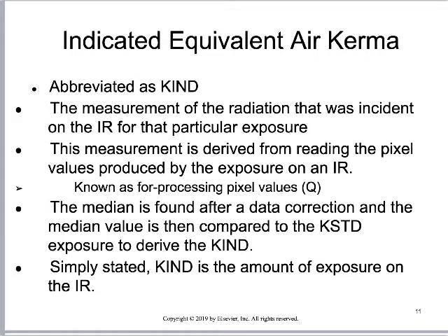Then there's the indicated equivalent air KERMA — this is a measurement of the radiation that actually hit the image receptor for a particular exposure. The K-STD was set up in a lab to determine what the system can do; the indicated one is what actually hit the image receptor when you hit go on the machine. They process the pixel values, find some median value, data correct, and figure out what is noise versus actual exposure. The simplest way: K-indicated, or K-IND, is the amount of exposure to the IR.